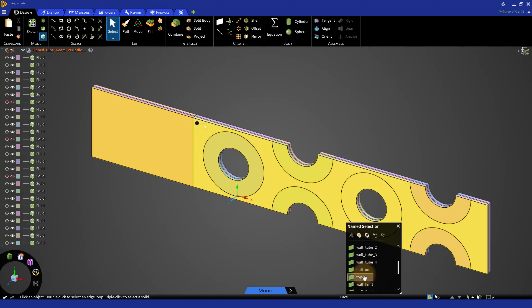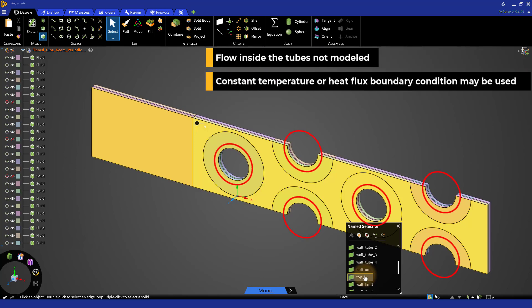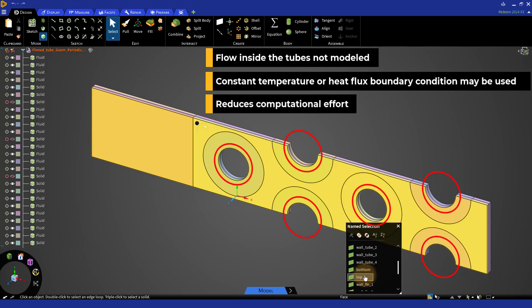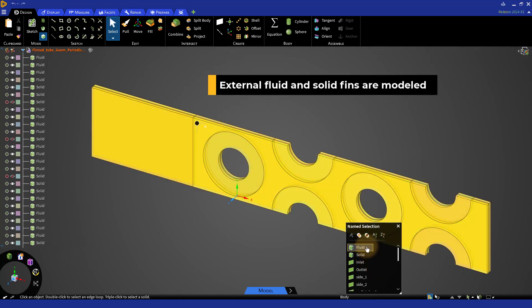This model will be used for simulating the heat transfer between the fluids occurring through the fins and tube walls. Instead of modeling the flow inside the tubes, a constant temperature or constant heat flux boundary condition may be used at the tube walls, which reduces the computational effort involved in solving the model since no internal fluid regions are required. However, the fluid flow over the fins and the tubes needs to be modeled, and hence the external fluid flow regions are included in the computational domain.